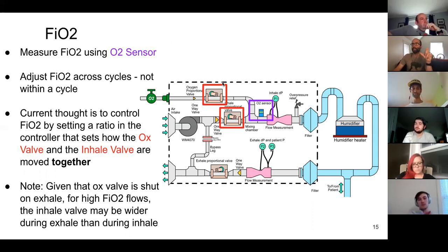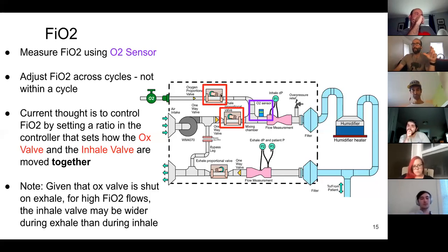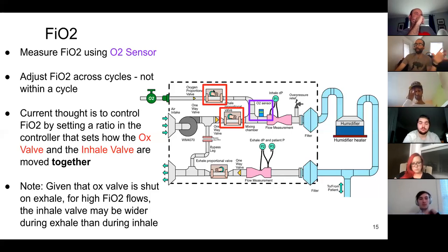So what we're going to do is establish a proportionality rate, right? Let's say our target FiO2 is 40%. And I'm going to talk about air and oxygen mixtures because it makes the math easier. Or actually, never mind. Let's say our target FiO2 is 60%, which works out to 50-50 air and oxygen. So at 60% FiO2, we're going to open both of these valves equally in parallel, right? And as those valves need to adjust pressure, they're going to move together. So if our controller says, hey, pressure's a little low, both of those valves are going to open 50% as much as they would if it was like the 100% case.